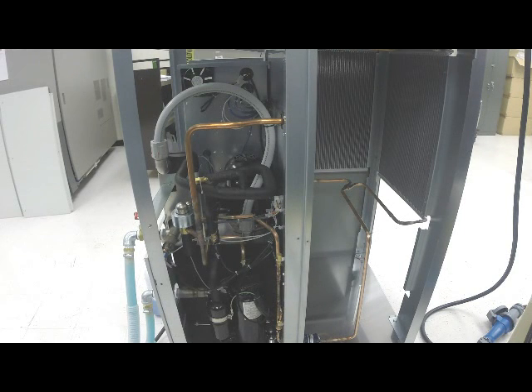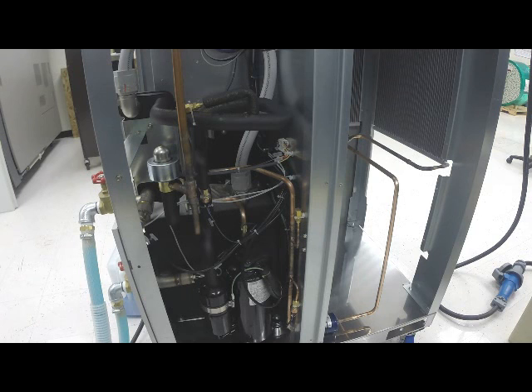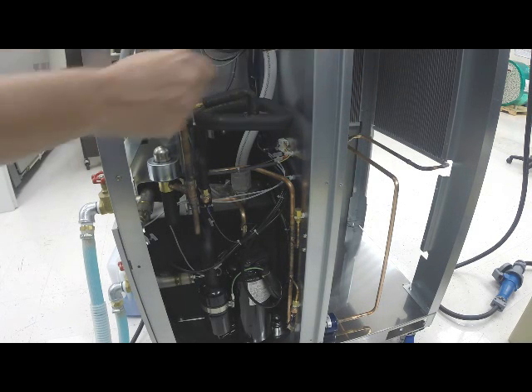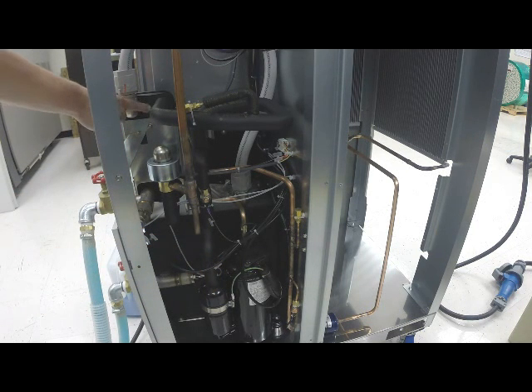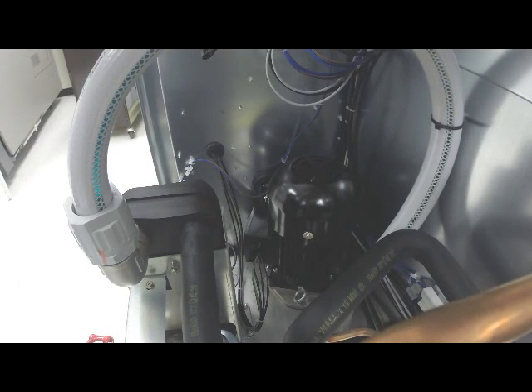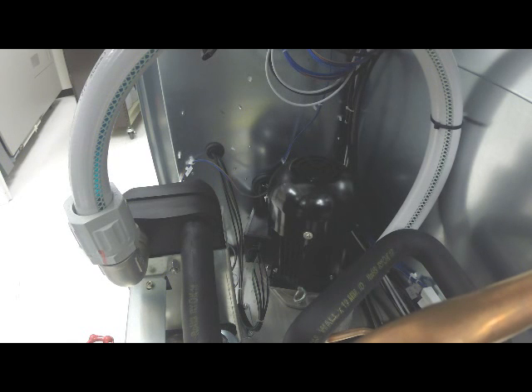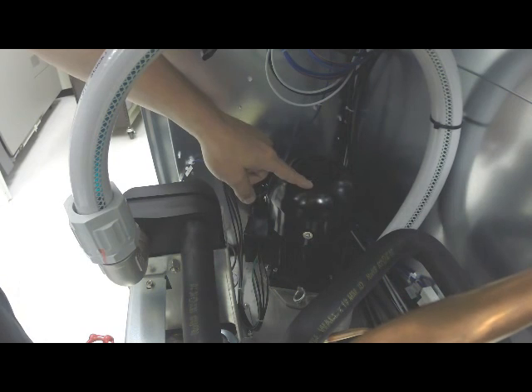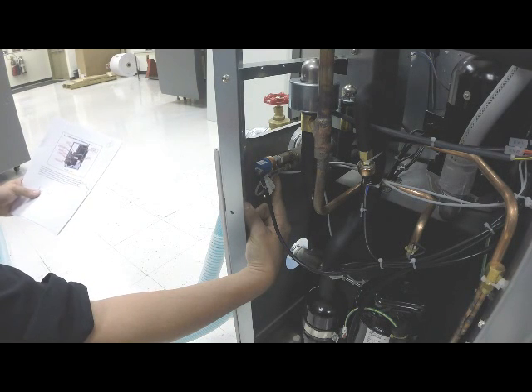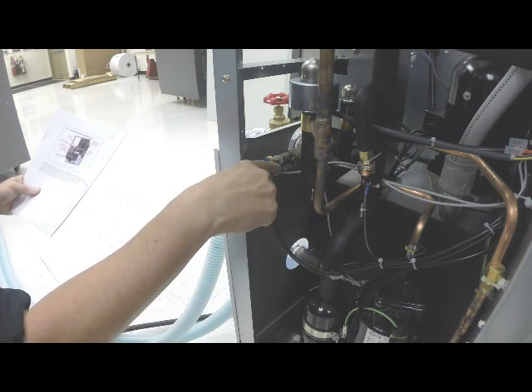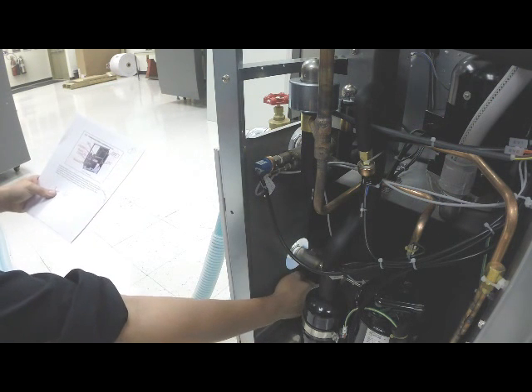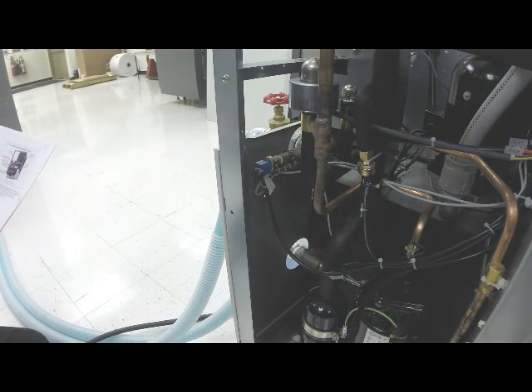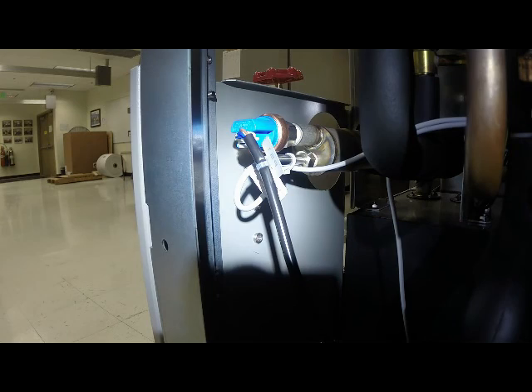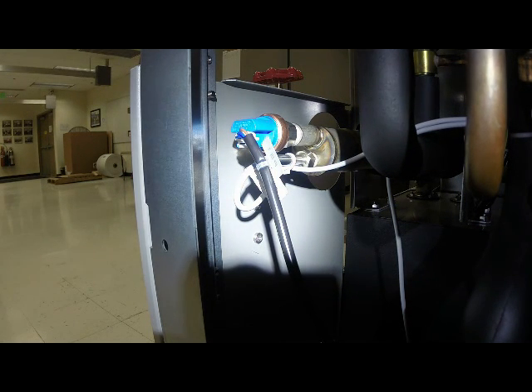Inside the system, you can see a system of copper pipes. All of these copper pipes contain the refrigerant circuit that we will not be servicing. The parts of the refrigeration circuit include the air-cooled condenser, the compressor, and the heat exchanger. More important to us is the circulating fluid system. These parts include the pump, temperature sensor PT1 on the bottom, pressure sensor PS1 on the top, and temperature sensor PT2 down below. This is a close-up view of the temperature sensor PT1 and pressure sensor PS1.